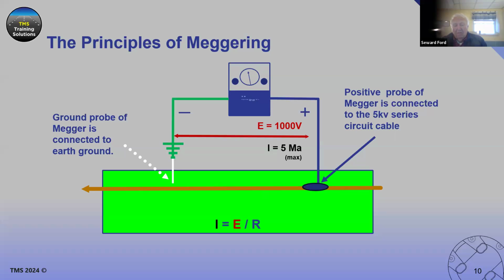And we have strategically placed out in the field a ground probe connected to the megger, and that's the negative terminal of the megger. And so that current, once it comes out from the cable, is going to gravitate and go through there, and we can measure that current. We measure the current, and then we can determine what the resistance is of that ground that current is traveling through. That's the general principle that we use.